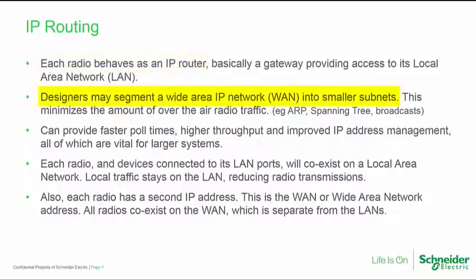Designers may segment a wide area IP network into smaller subnets. This can provide faster poll times, higher throughput, or improved IP address management, all of which are vital for larger systems. Each radio and devices connected to its physical LAN ports will exist as part of a unique local area network. Local traffic stays on the LAN, reducing radio transmissions.